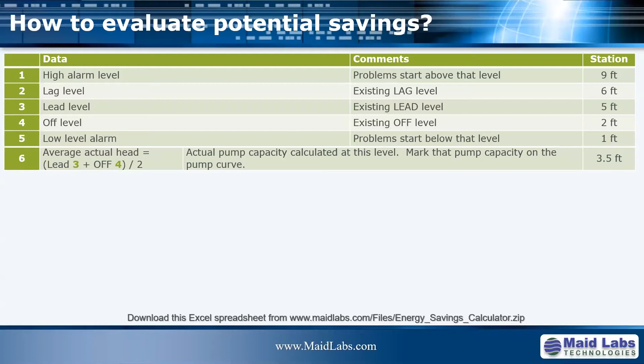Let's say that's just for the calculation here. Next step after that is, okay, at what level we could run these pumps and what would be the average level of operation. So let's imagine that we could start the pump when the flow rate is low, almost at the high alarm level, and we would stop them 3 feet lower like it was the case before, which by coincidence arrives at the lag level. So that's again a 3 feet difference. And the average between 9 and 6 gave us 7.5. So we have a 4 feet difference in head.